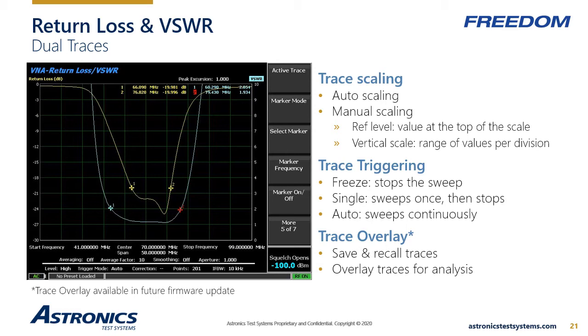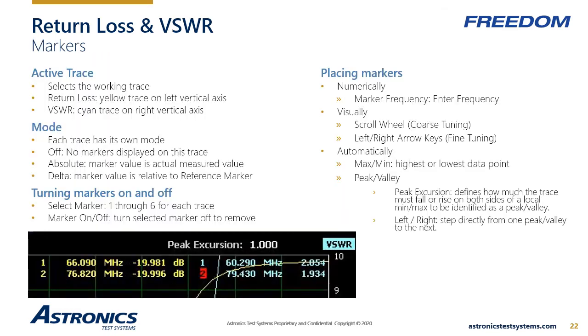Your investment is future-proof. Up to 6 markers are available for each trace, for a total of 12 markers. These markers can display absolute measurements or measurements relative to a reference marker. Markers can be placed at user-specified frequencies or placed visually by scrolling or jumping between peaks and valleys. The user can even tell the system what constitutes a peak or valley by specifying an excursion value. You can skip over small peaks or valleys and jump between tall peaks and valleys.